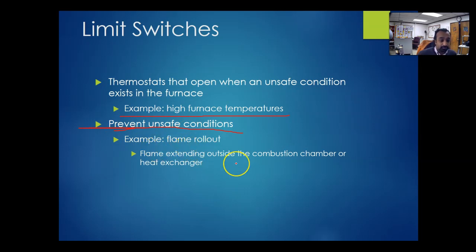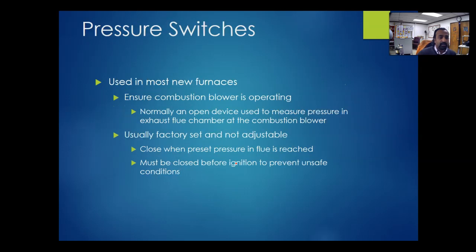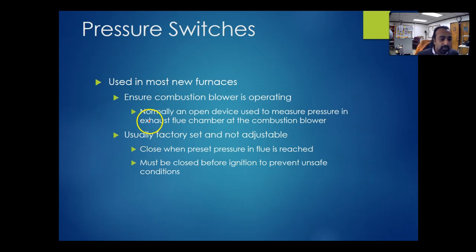One example of a safety issue is flame rollout. Also, the direction of air is very important — if you accidentally reverse the direction inside the duct, you might be blowing air into the furnace and forcing the flame to come outside rather than staying inside. Pressure switches are very important, especially for steam systems. They are also used to prove the flow of air — if air is flowing, it will produce some kind of negative pressure, ensuring the combustion blower is operating.